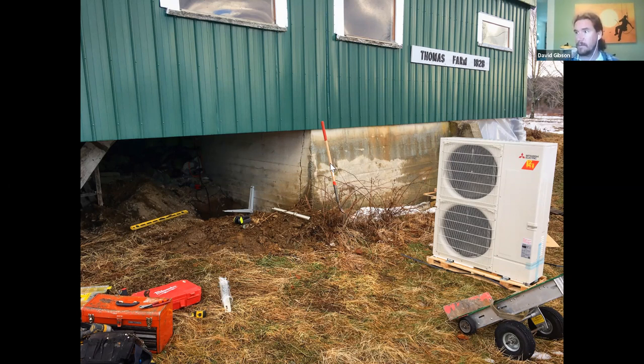They can either be mounted to a concrete foundation wall or on a ground-mounted stand with a precast concrete pad and some metal brackets to get them up off the ground. Generally, they don't recommend mounting them to wooden stud walls because the vibration from the outdoor unit can carry through to inside and can be quite loud inside the house. And so generally we avoid mounting them to wooden stud walls and only mount them to concrete foundations or just on the ground.